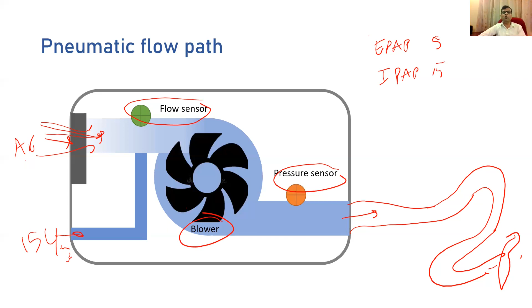Now, when you add oxygen, there is a certain port, and you can add probably about 15 liters. In most of the devices, certain devices can add 30 liters. Even if you add 30, even 40, the room air entrainment is kind of inevitable. When the blower works, it's designed to get room air to pressurize this limb. So that is the biggest issue in using these devices when you want to give oxygen.